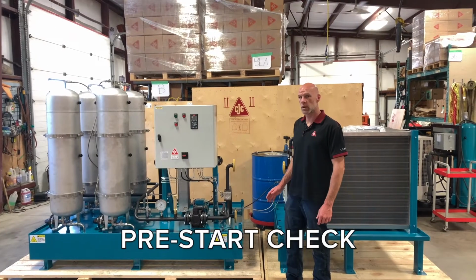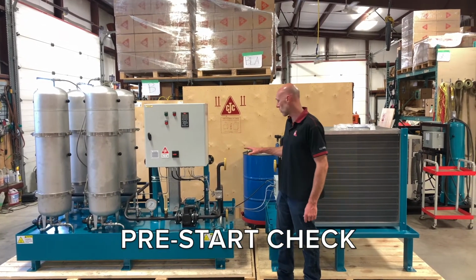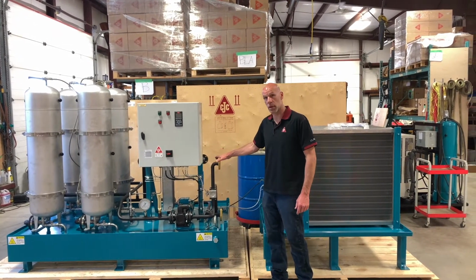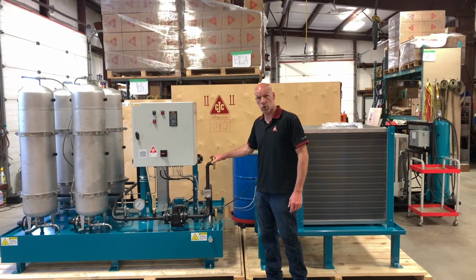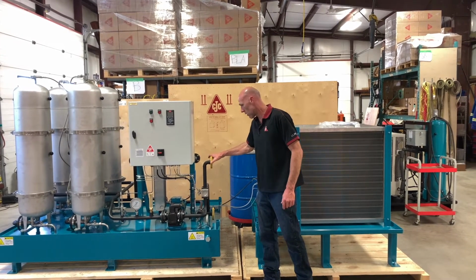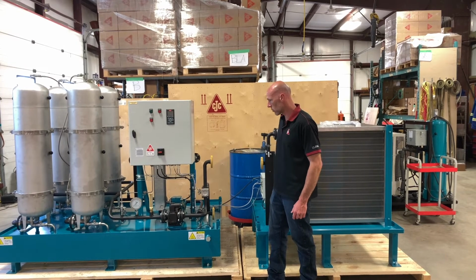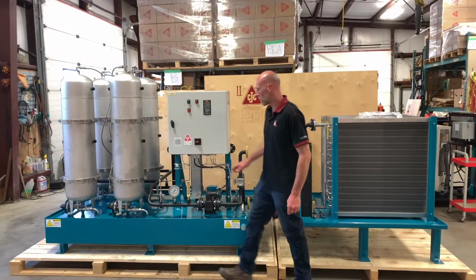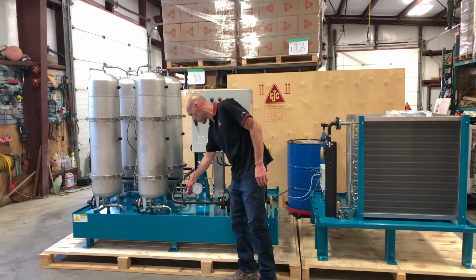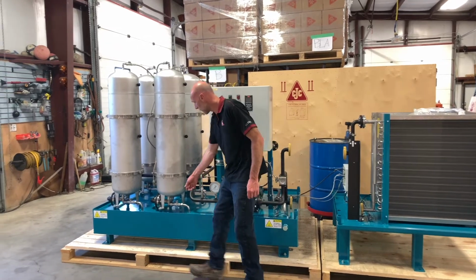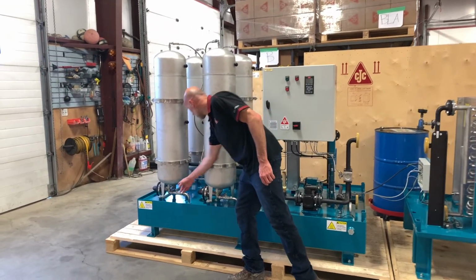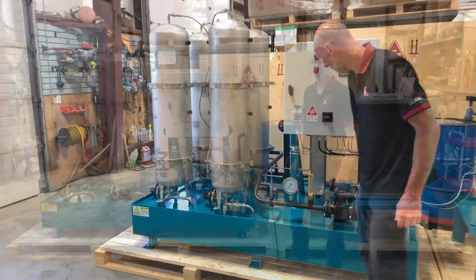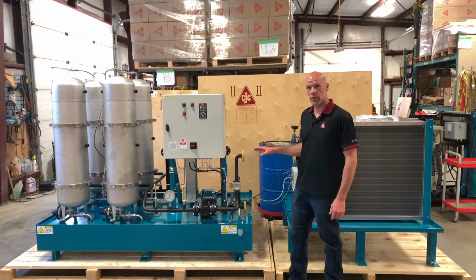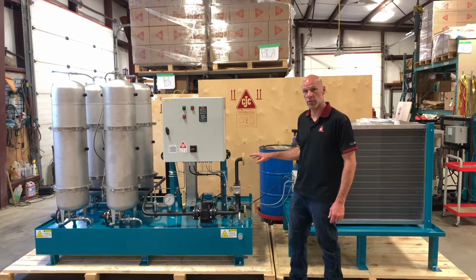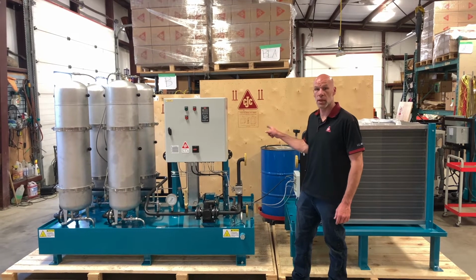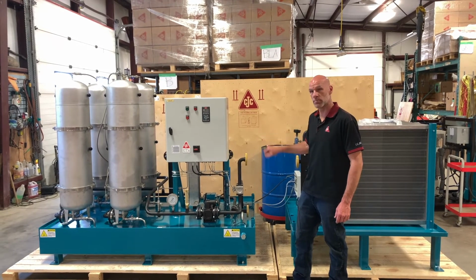Before starting the unit up, make sure you go through your oil connections, make sure all your pipes and your flanges, that the bolts are tight and that they've each been torqued uniformly. You want to make sure that your sample valve is closed, that your drain valves are closed on the 4 filter towers. Once you've ensured all the valves are closed and all the connections are tight, you can then proceed to open the main inlet and outlet valves.